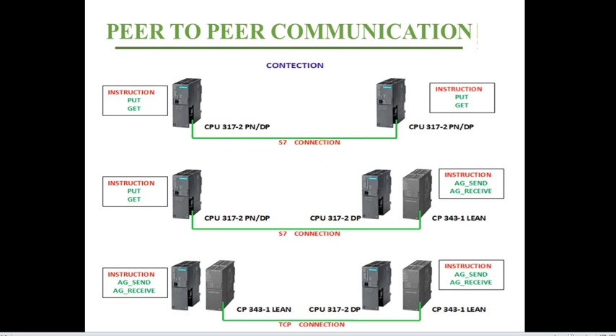The second layout is where the first PLC has a Profinet port but the second doesn't. We can use a communication processor module to connect the two PLCs. On one side the instruction is PUT/GET, and on the other side we use AG_SEND and AG_RECV.